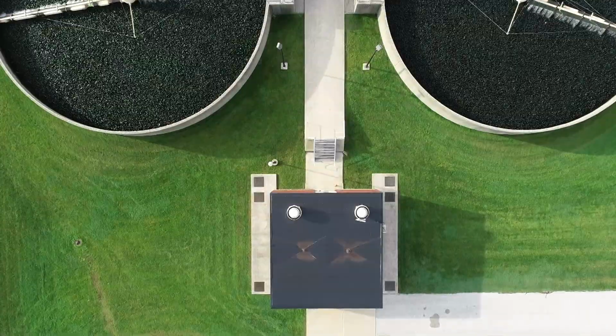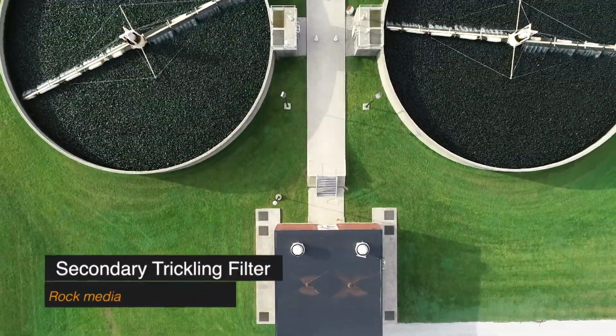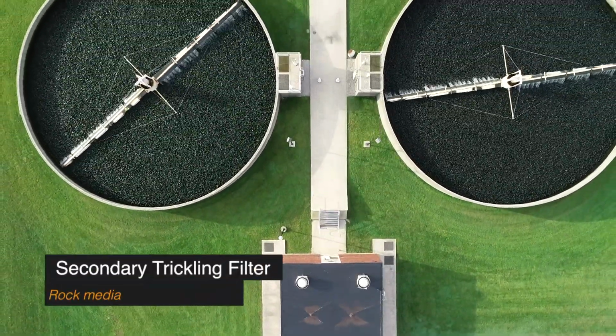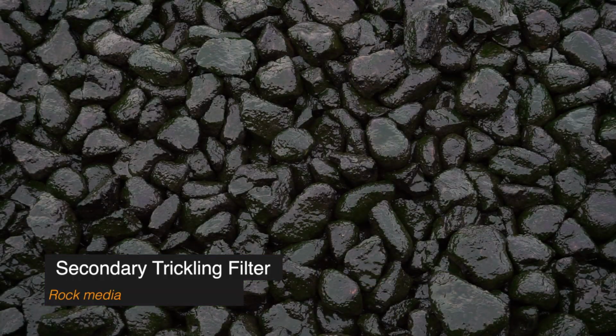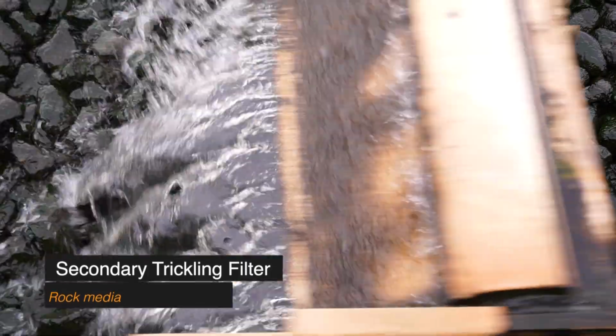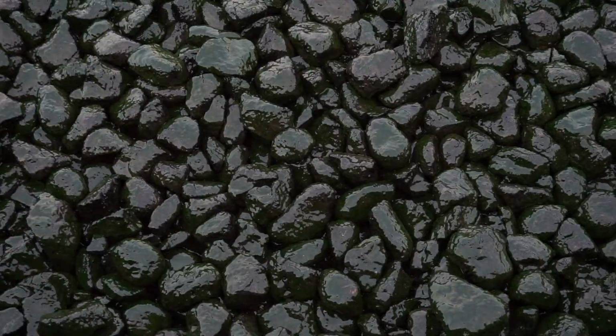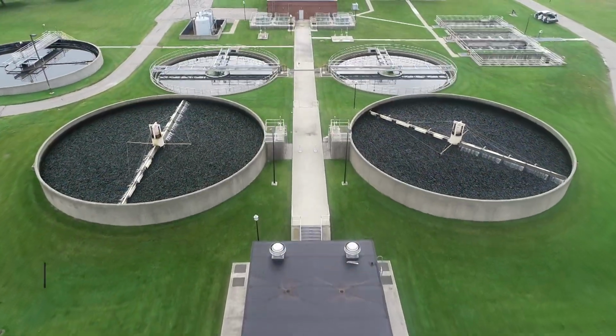We have a 2-stage trickling filter system. After it flows through the first trickling filter, it flows through a second trickling filter and clarifier. The difference here is the media. The secondary trickling filter has the original rock media, which provides about 11 square foot of surface area per cubic foot of space. Before the water enters the secondary clarifier, it goes to a flocculation basin.